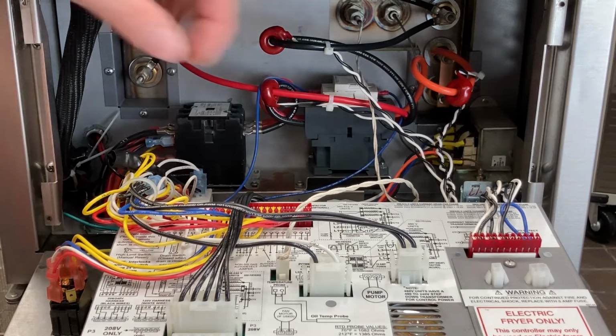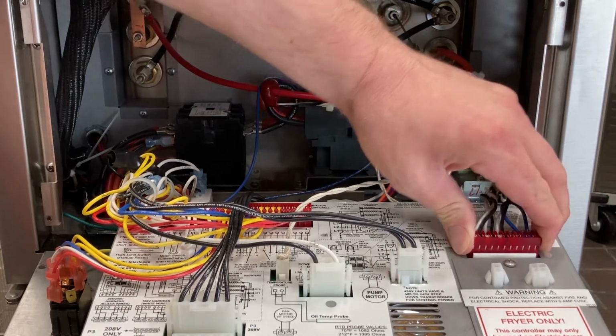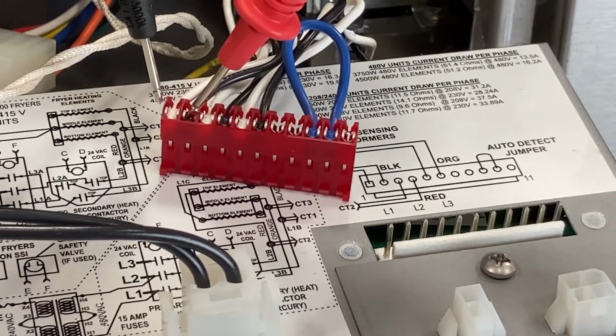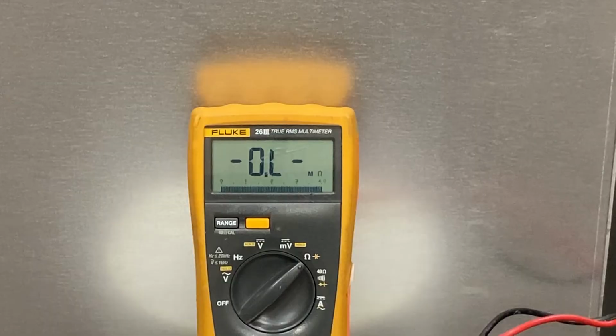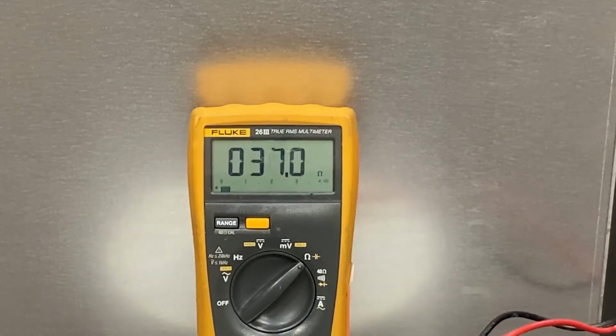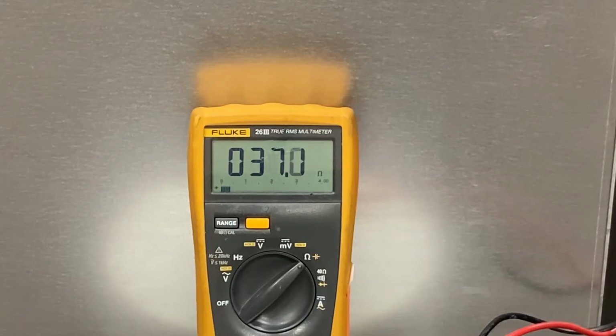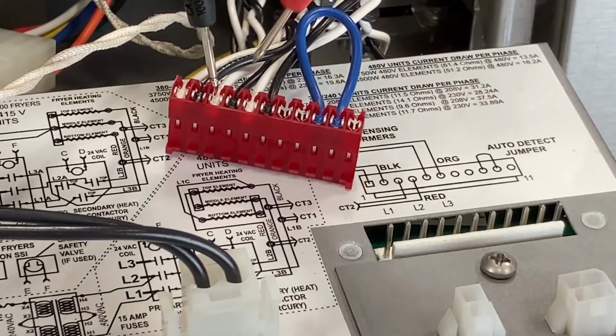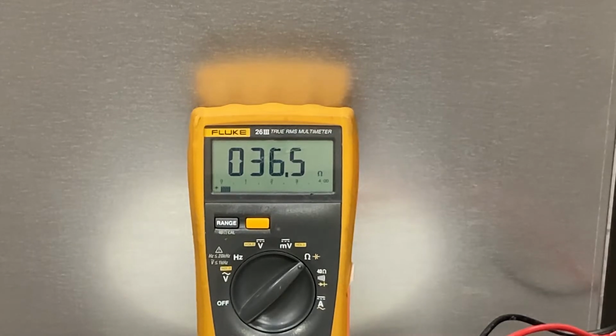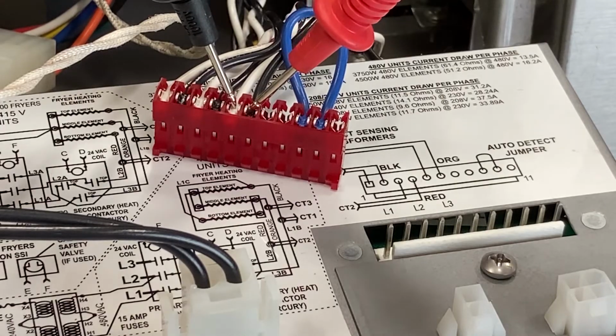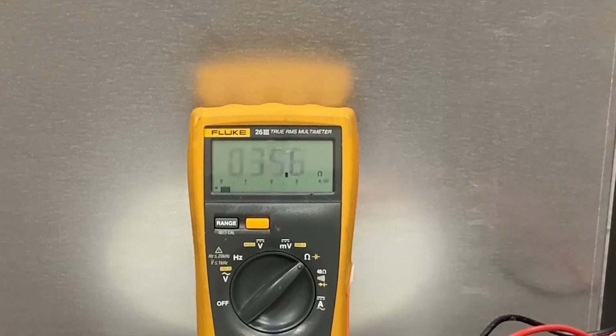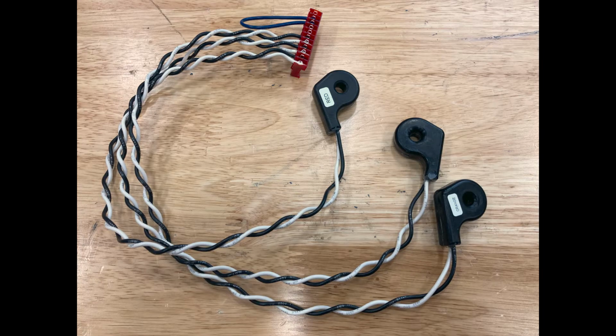To check amp sensors, unplug them at the back of the control and take a resistance reading between each set of wires for all three sensors. The reading should be 35 ohms plus or minus 3.5 ohms for each sensor. After taking all three readings, if a faulty amp sensor is found, all three sensors will have to be replaced together as it comes as one complete harness.